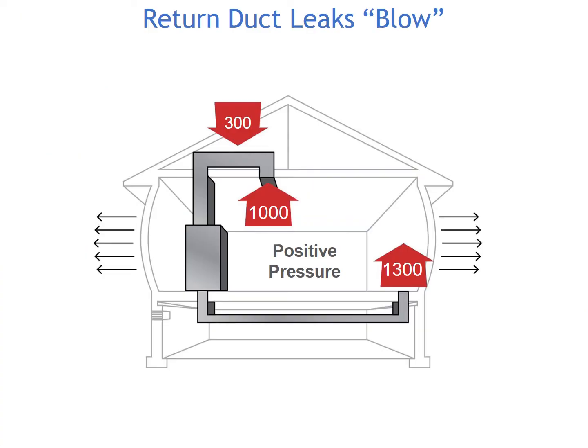Take a look at this diagram here. You can see 1,000 CFM being sucked into the return, but it's also sucking in an additional 300 CFM from the attic space. So now we have 1,300 CFM coming out into the building, and now we have everything pressurized. This is a home, and it may not be as big of a deal, depending on what you're pulling in from the attic, if you pressurize the home because you're not drawing in allergens and other things from outside. But think of a commercial building. What happens to spaces if you have a unit that has this situation, with positive pressure going on? You may be pulling odors from a kitchen, or other odors and smells, from one unit and pushing them to another unit and other occupants that may not be welcome to those odors and smells.